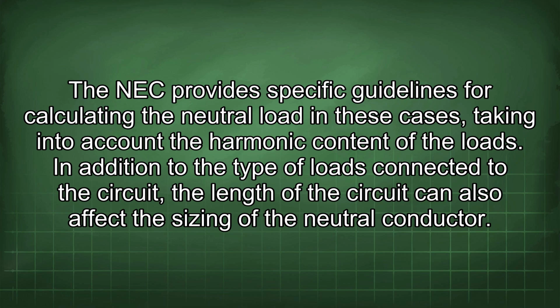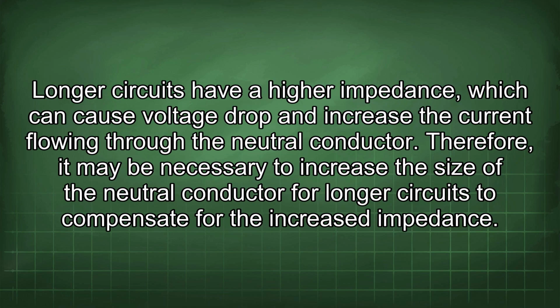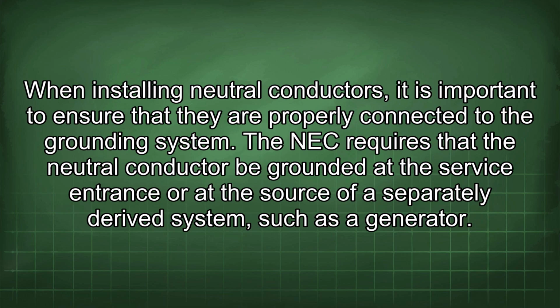content of the loads. In addition to the type of loads connected to the circuit, the length of the circuit can also affect the sizing of the neutral conductor. Longer circuits have a higher impedance, which can cause voltage drop and increase the current flowing through the neutral conductor. Therefore, it may be necessary to increase the size of the neutral conductor for longer circuits to compensate for the increased impedance. When installing neutral conductors, it is important to ensure that they are properly connected to the grounding system.